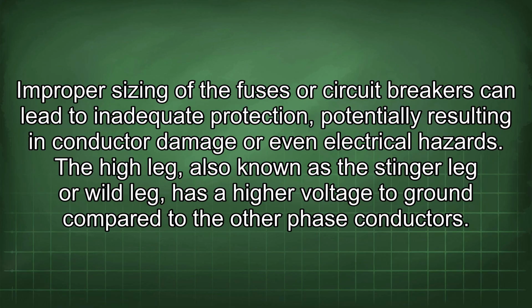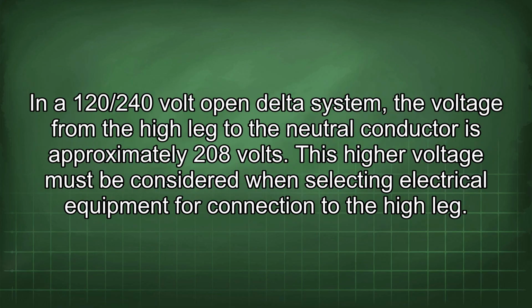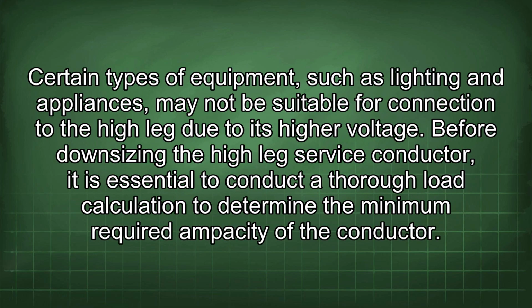electrical hazards. The high leg, also known as the stinger leg or wild leg, has a higher voltage to ground compared to the other phase conductors. In a 120/240 volt open delta system, the voltage from the high leg to the neutral conductor is approximately 208 volts. This higher voltage must be considered when selecting electrical equipment for connection to the high leg.